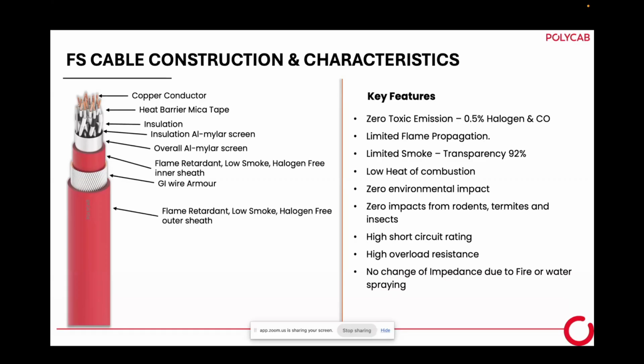Sometimes we manufacture different kinds of fire survival cable: power cable, instrumentation cable, communication cable, and data cable. Wherever instrumentation or data cables are there, a mylar insulation screen, sorry, an EMI screen is there. Otherwise, there will be an inner sheath, inner jacket, which is low smoke, halogen free, flame retardant. Over that, there will be an armor, GI wire or steel armor, and over that there is a flame retardant, low smoke, halogen free jacket, which does not produce much toxicity.